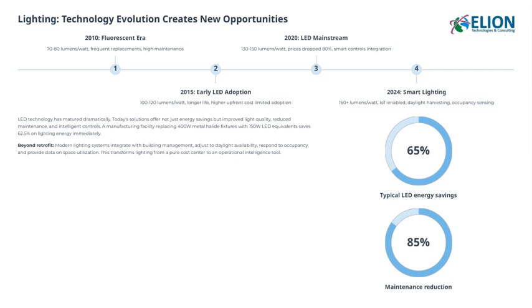The key takeaway here is that LED technology has matured dramatically, offering much more than energy savings. Modern solutions improve light quality, reduce maintenance, and enable intelligent controls. For example, consider a manufacturing facility replacing 400 W metal halide fixtures with 150 W LED equivalents. This results in immediate energy savings of about 62.5%.